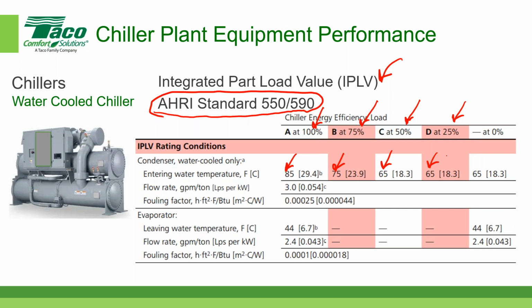Okay, so now we're going to actually look at these values here. This is the A, B, and C values. This is the performance of the chiller at these reduced capacities. In other words, we're going to look at a value associated with a kW per ton value when the chiller is 75% loaded, at a condenser water entering temperature of 75 degrees. I know it gets a little confusing. So they're looking at two values at the same time, and that's how they calculate the IPLV.